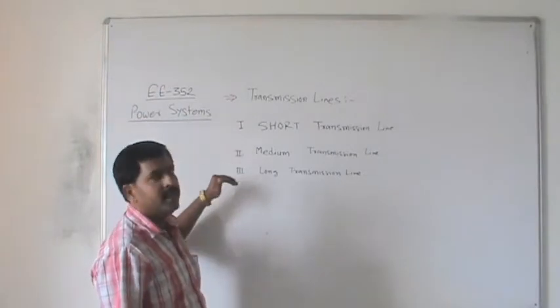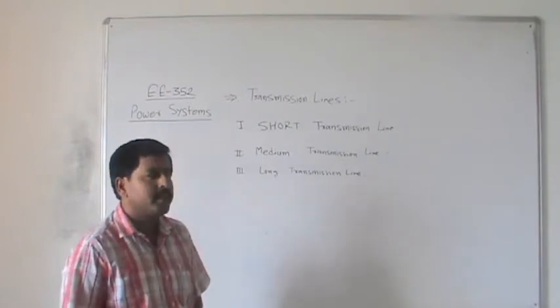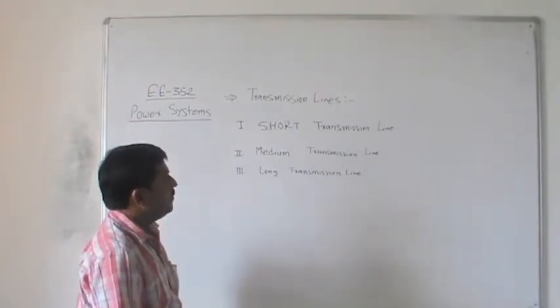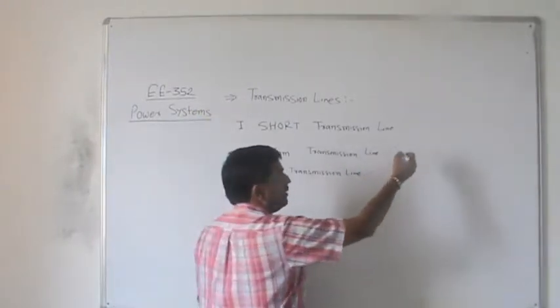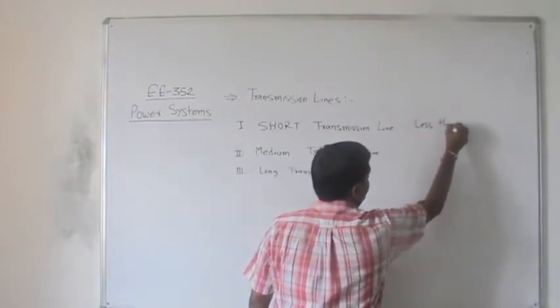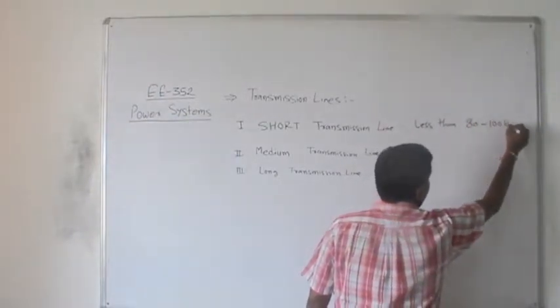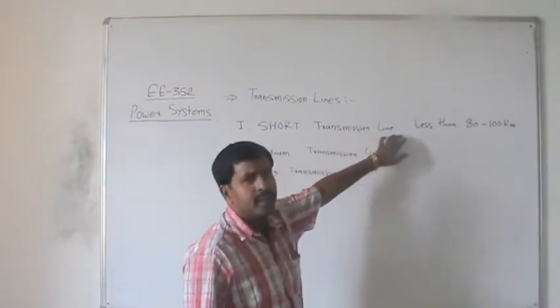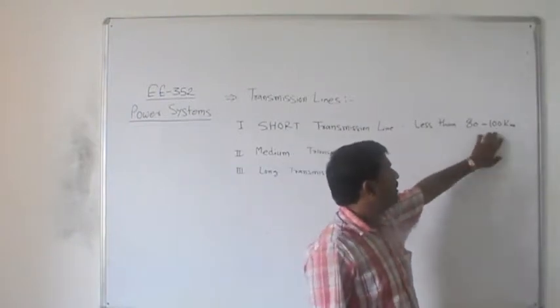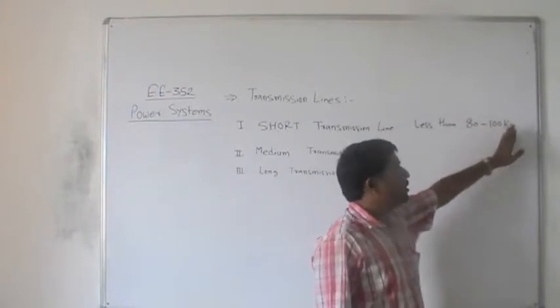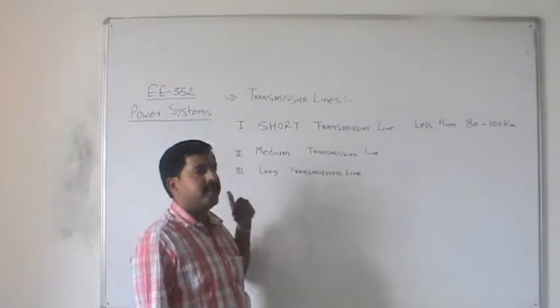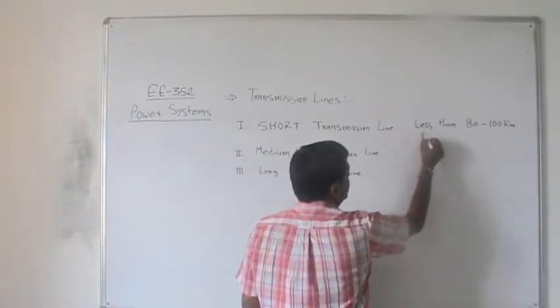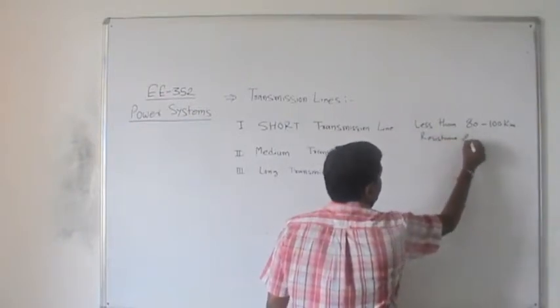How do we classify transmission lines into these categories? It depends mainly on the distance or power carried from one point to another. If the distance is less than 80 to 100 km, the line is known as a short transmission line. For short transmission lines, we consider only resistance and inductance as parameters.